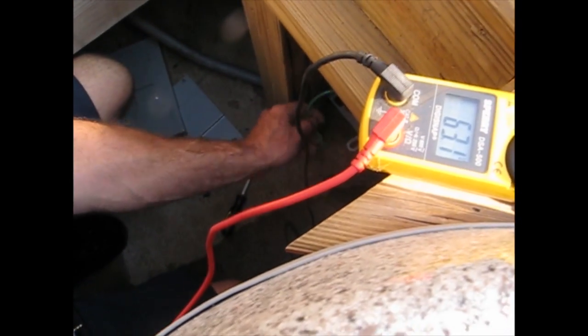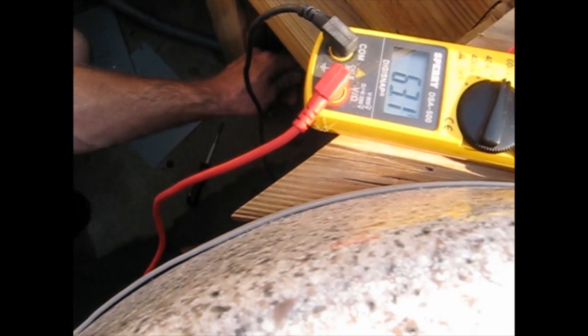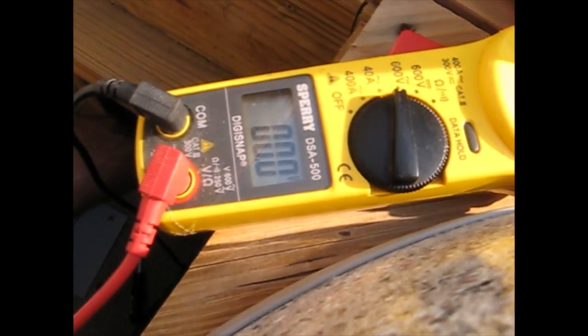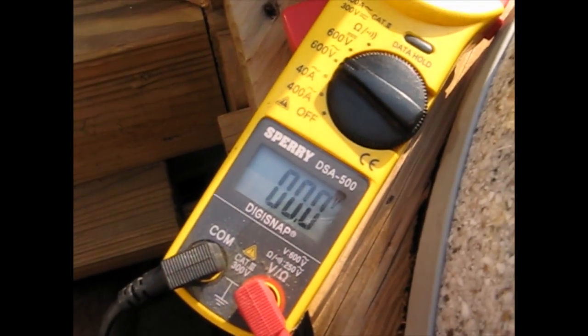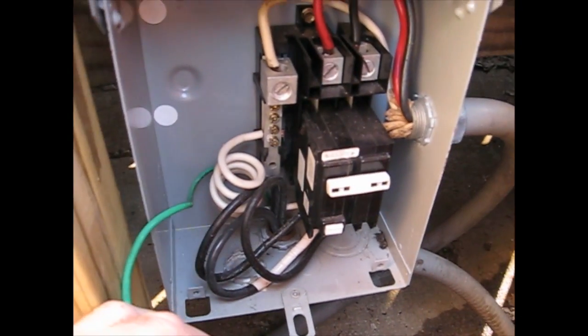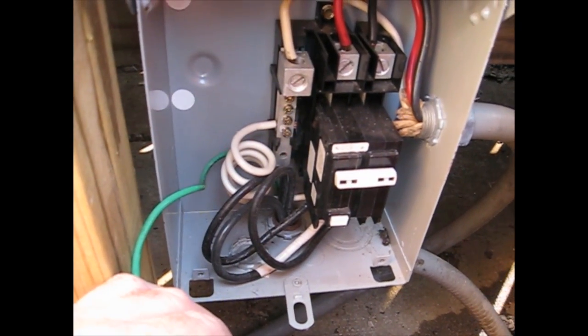See, I'm going to hook my ground up. See if I can do that. Now, when I hook this ground up, let's see if the voltage goes away. Look at that. It does. So when I touch that to ground, the voltage goes away. Just as so. So that's a sign when you see that. No ground with the GFI in.